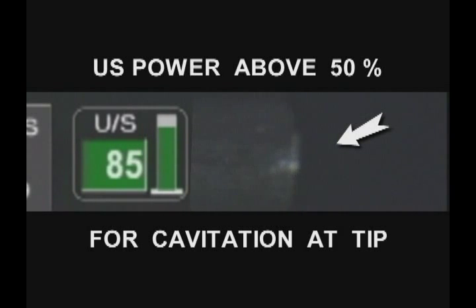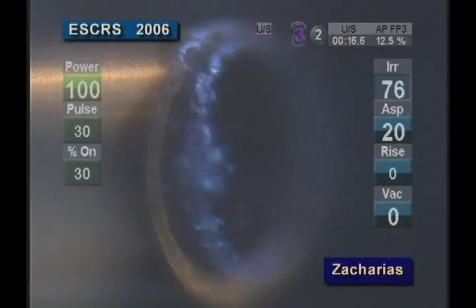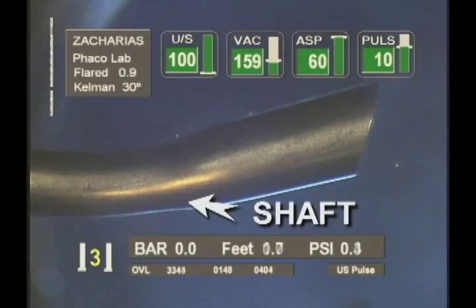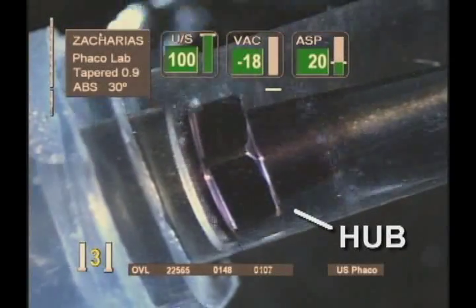We revealed that cavitation mainly occurs in close proximity to the tip of the phaco needle, and that it only appears at high ultrasonic powers of 50% or more. We also found that cavitation not only occurs at the tip of the phaco needle, but also along the shaft and in proximity to the hub at the proximal portion.